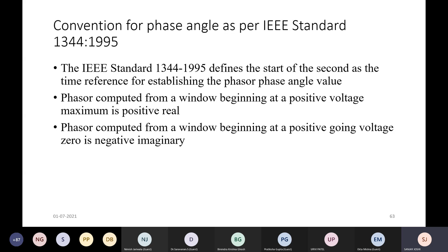There is a convention for phase angle as per the standard, shown here. If sample number 0 is at the start of the positive cycle, say there are 12 samples, sample number 0 to sample number 11, that calculates the phasor. In that case, if sample number 0 is at the start of the positive cycle of voltage, that phasor calculation will be assigned an angle of -90. Similarly, in the adjacent figure, if sample number 0, the first sample in the moving window, is at the peak of the positive half cycle, then that phasor calculation will be assigned an angle of 0. This is the convention to be followed by all PMU manufacturers.